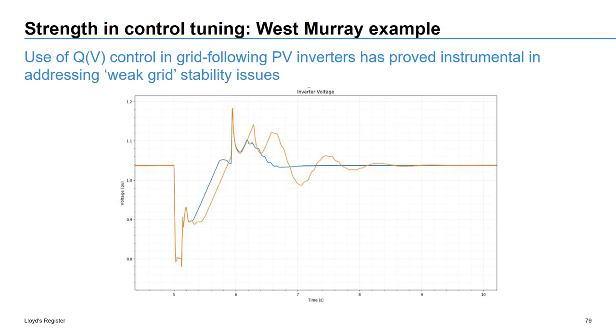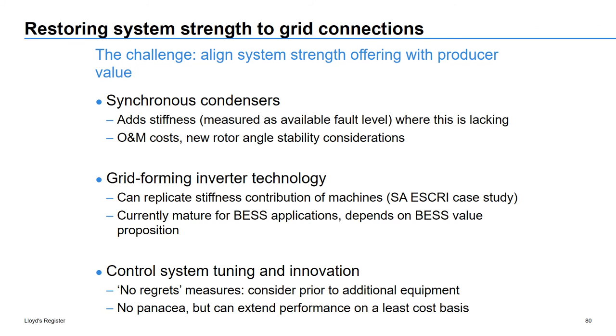So in summary, the challenge that we face in regard to system strength with grid connections is to align the system strength that the plant can offer and that the system requires with the value proposition for stakeholders in the commercial and regulatory environment of our national market. And at high level, we have the three technical approaches to system strength currently. One based on synchronous condensers, the drop-in equipment solution, which provides that additional stiffness by way of a traditional synchronous machine solution.